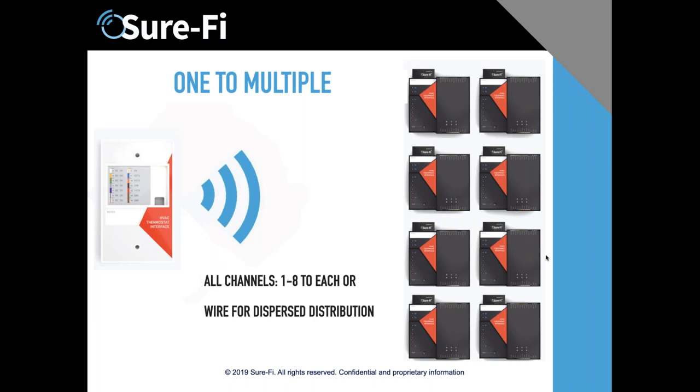Now, these are at this point normally open contacts, and we've done quite a few interesting installations with them, specifically for things like Knox boxes where you open those up, you push one button, and you've got a bunch of locations you want to open up all at once. So when the fire department rolls up, everything opens. There's been a really interesting application that way. I've also used it on perimeter alarms, alarms for water and temperature sensors in remote cabins and things like that. So this is an interesting one, using a one to multiple, sending 8 relays out, 2 relays back.